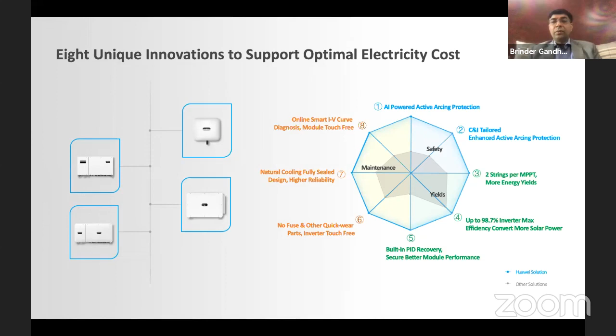Coming to active safety, electric arcing is a very important factor threatening the safety of a PV system. How it happens is that there's a breakdown of the air, causing prolonged electrical discharge through the air. The causes of this electric arcing could be solder joints within the modules, broken PV cables, or loosened PV connectors. If arcing happens, the temperature can reach up to 3000 degrees, and it can easily set fire to any component or even the roof.